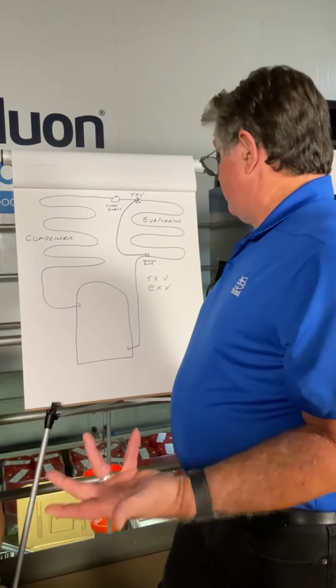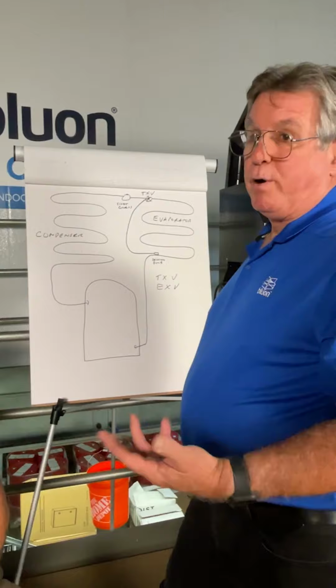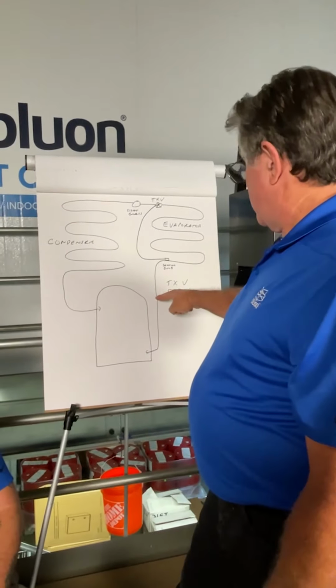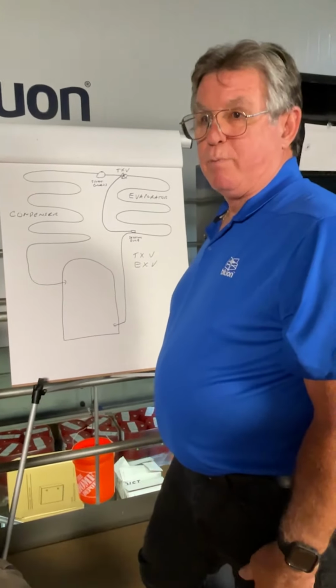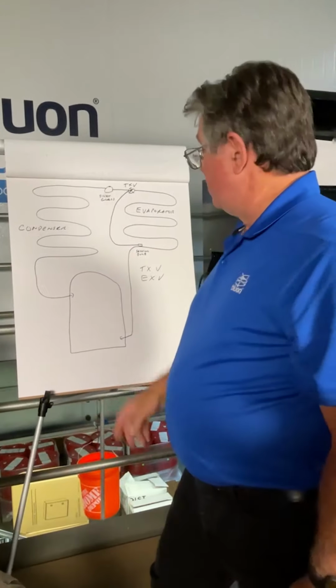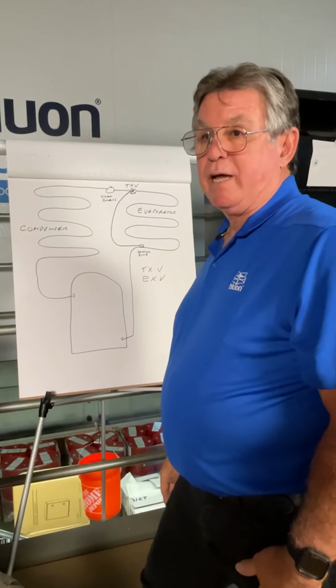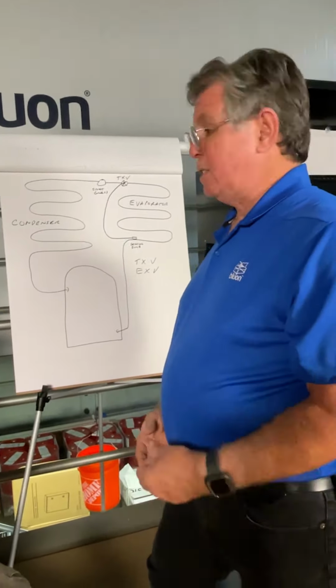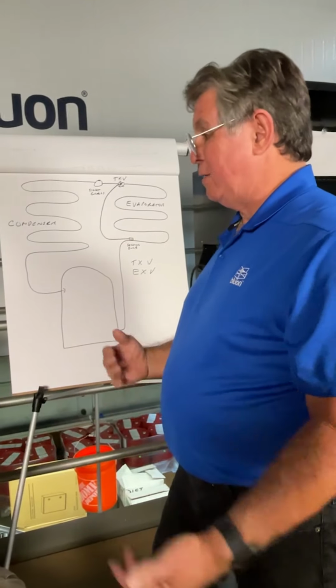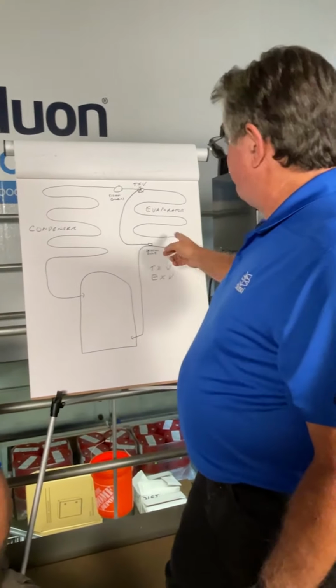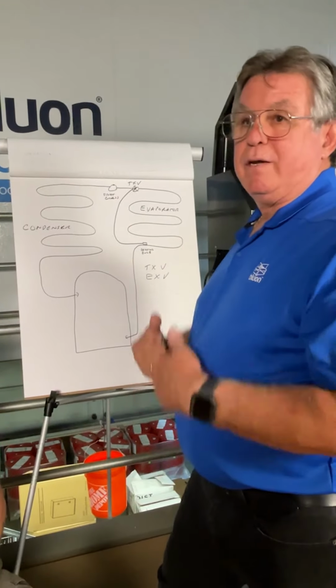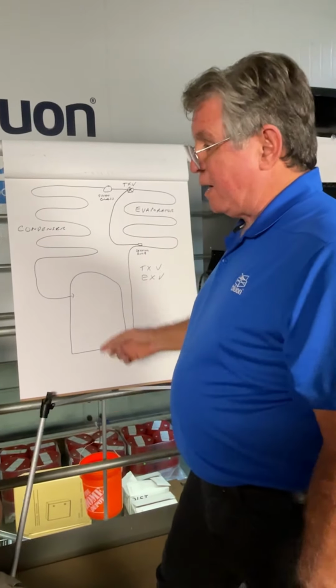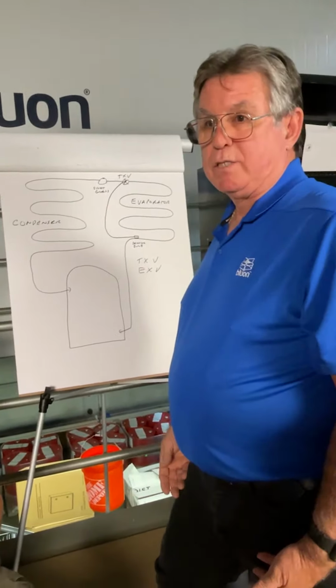All right. I mean, theoretically, in a perfect world, we would boil off all the refrigerant right before it went into the compressor so that we were getting the most work out of our coil and everything else. The problem with that is because valves are kind of sloppy and they can only turn down so far. If we go too far, then under the right conditions, we could cause floodback and do damage to the compressor.